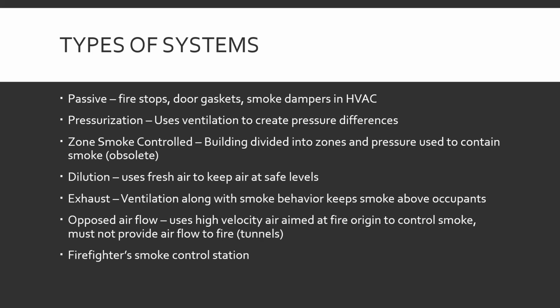Opposed airflow uses high velocity air aimed at a fire origin to control smoke, but it must not provide airflow to the fire, because if you blow on a fire, turn a fan on a fire, it's going to make it worse because you're feeding it. But these use, as it says, think of big fans, like long road tunnels, railroad tunnels, subway tunnels, air blowing down the tunnel, pressurizing it, and at the other end of the tunnel, there's an outlet to let all the smoke out into the atmosphere. So you're blowing all the smoke down whatever tube we're talking about, and it's going out.